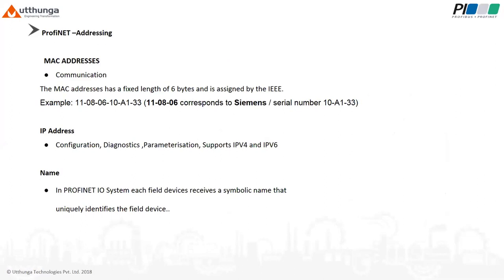Addressing in PROFINET is divided into 3 topics: MAC address, IP address, and name. MAC address is the hardware address of PROFINET devices. MAC address has a fixed length of 6 bytes and is assigned by IEEE. The format is hexadecimal. The first 3 bytes indicate the manufacturer. The rest is freely assignable by the vendor. In the example you can also see the first three bytes are assigned by IEEE and the other 3 are assigned by Siemens or any vendor.